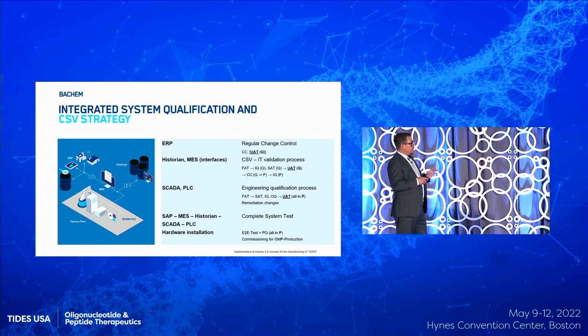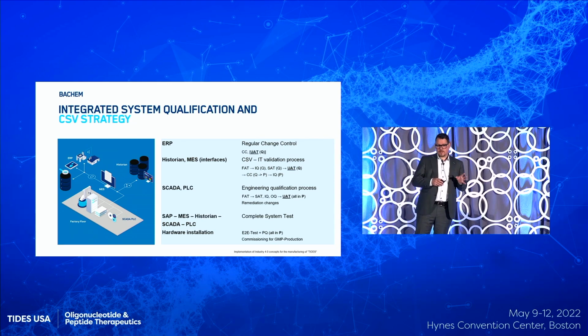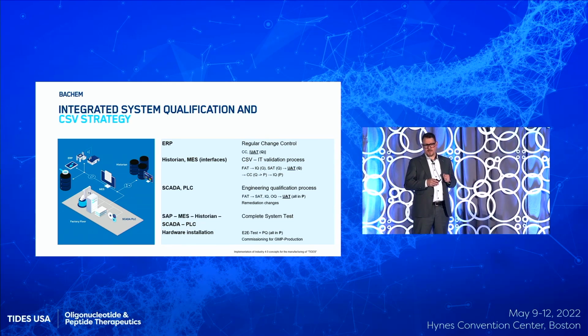And the IT/OT part with the historian and MES, that was a computer system validation with factory acceptance test, IQ in the Q system, site acceptance test, user acceptance test, and then a change into the productive system with an IQ. And SCADA PLC, this is the classical equipment qualification: factory acceptance test, site acceptance test, IQ/OQ, and a user acceptance test in the productive system.